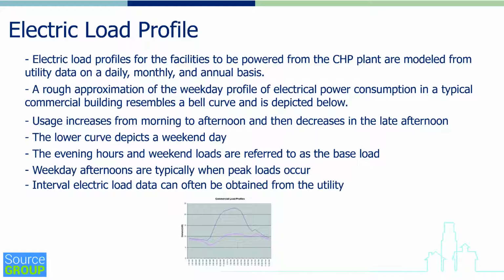Interval electric load data can often be obtained from the utility. If the utility is contacted and you request it, many times, depending on the type of service you have, but if you certainly have HTS, in some cases LPL, large power lighting, the utility will actually furnish you interval data indicating over time what the electric load is at a given point in time during each day.